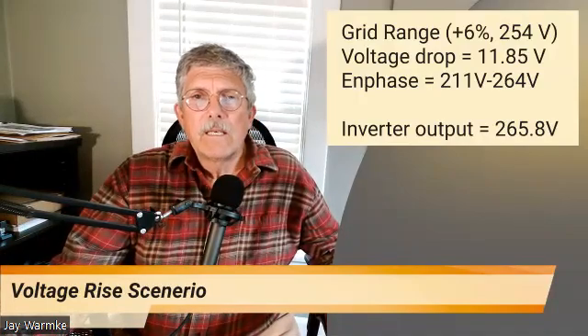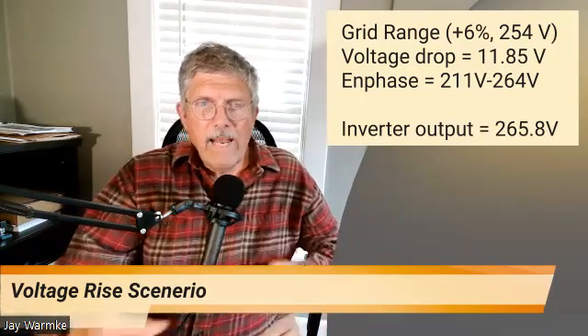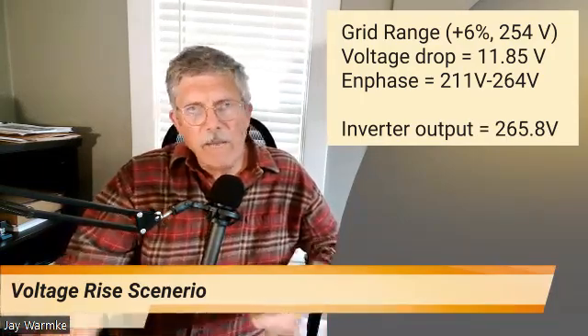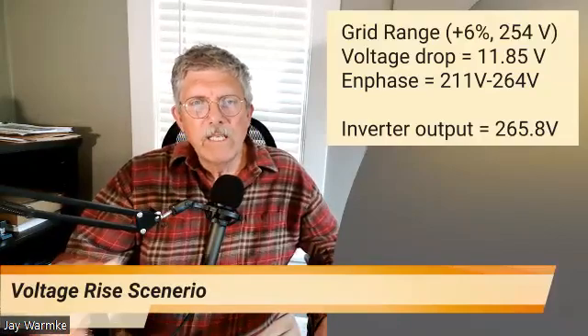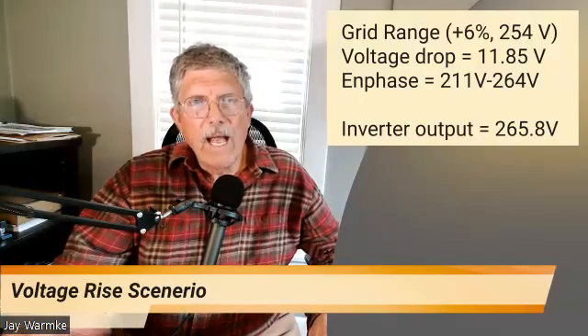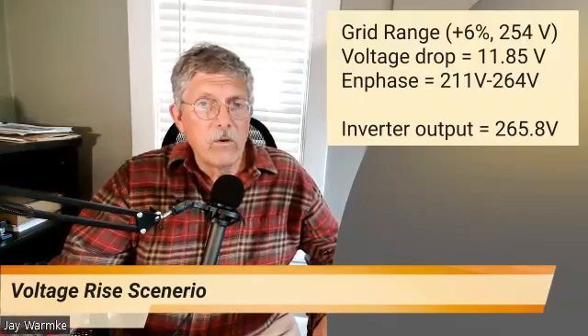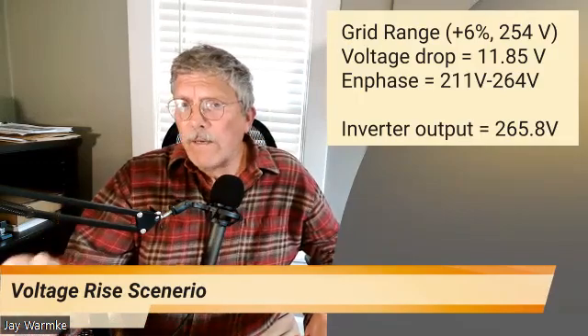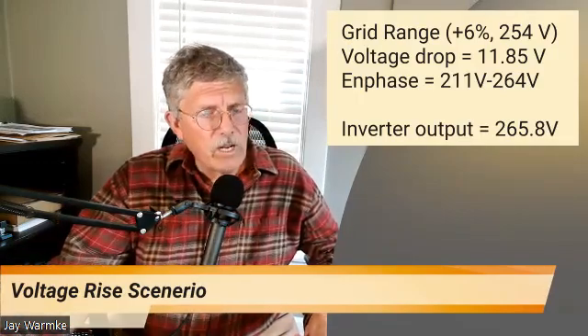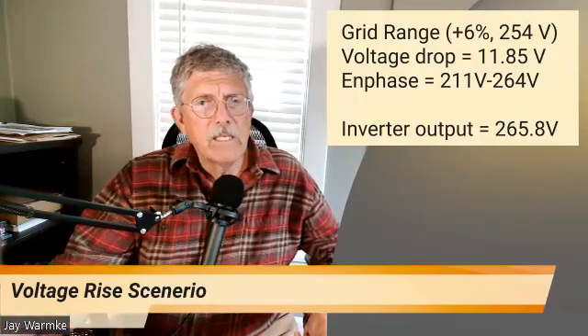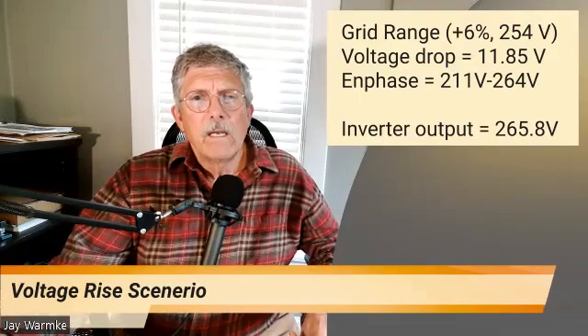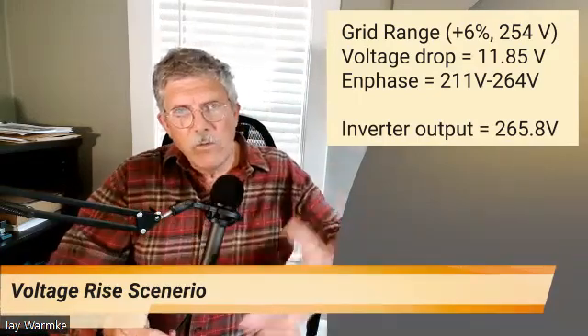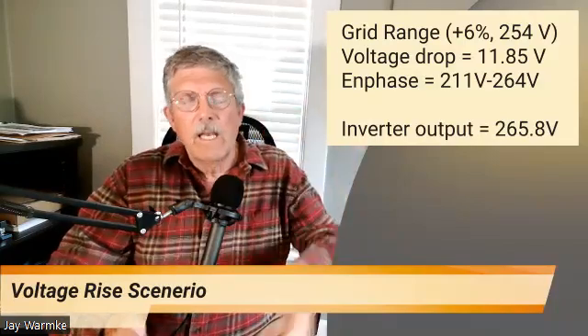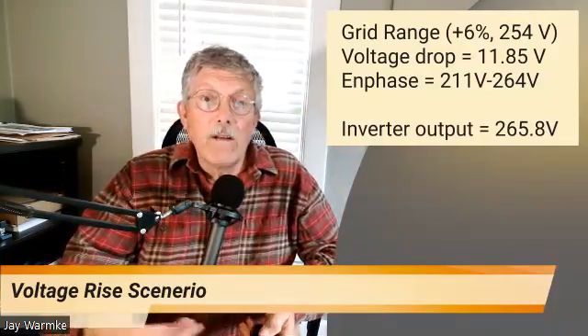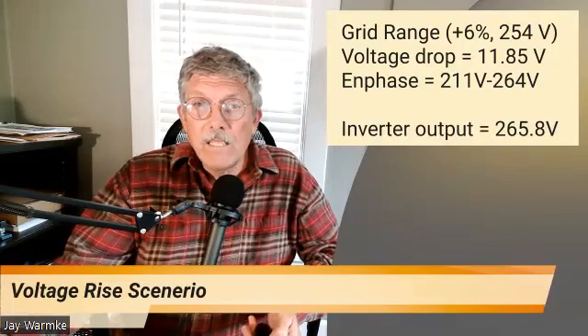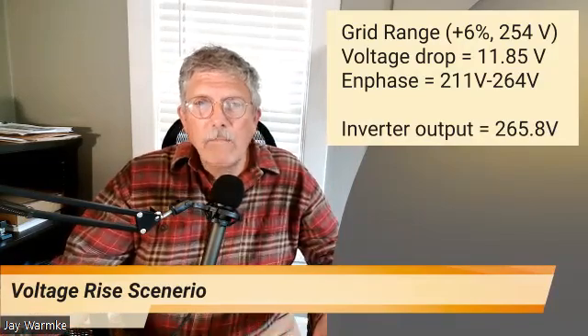It's going to disconnect. Now it will wait, look for the grid signal, and then go through a 5-minute handshake and then reestablish connection. If the grid voltage has dropped back down, then it's probably going to operate normally at that point. But if you were experiencing this where the inverters seem to shut off periodically, then reestablish connection, it may be a case of voltage rise. Because of the fluctuations of voltage on the grid, you're starting to see your microinverters kick off. And the best solution there is to avoid the problem by putting in big enough cable.